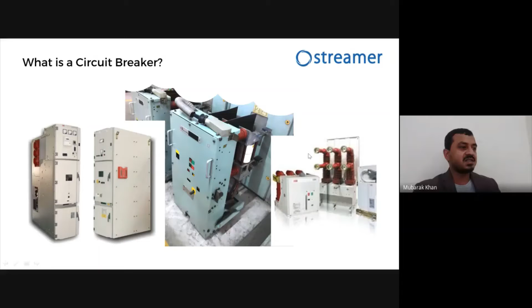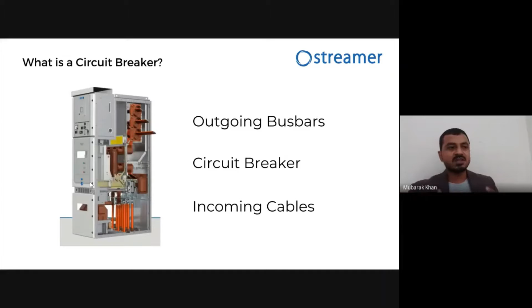Okay, so as we saw in this slide before also, the circuit breaker panel contains outgoing bus bars, the circuit breaker itself, and incoming cables. As you can see here, this is a bus bar chamber. So the bus bars are going out. This is normally in normal conditions. This is actually the outgoing of the circuit. Okay, and then this is the cable chamber. In the cable chamber, there are the incoming cables, etc. And in the circuit breaker chamber, there are the circuit breaker and its connections.